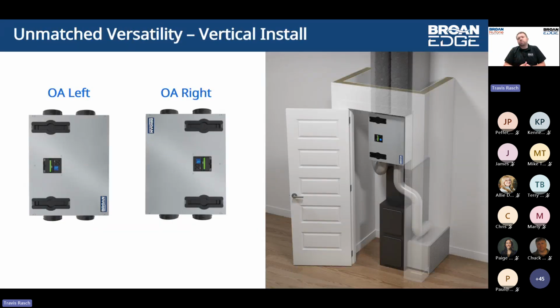Kind of diving back to your question, and again, these units will have lower CFM output than some of our current models. So managing expectations there, do know that any additional elbow, or number of elbows for that matter, or lengths, will certainly reduce your airflow output. So again, be mindful when you're in that design phase. Not that you're expecting, in this type of application, to get the full 120 out of it.